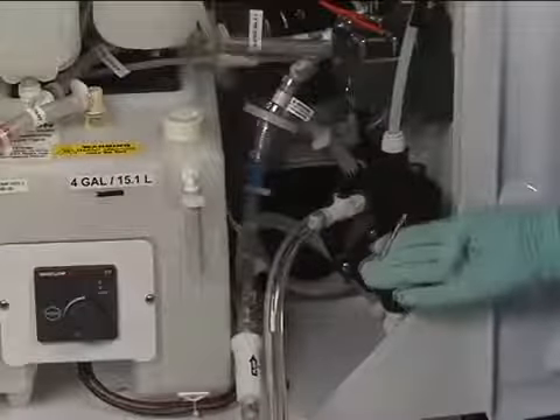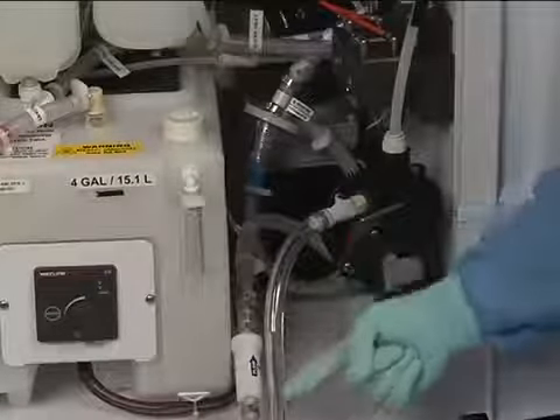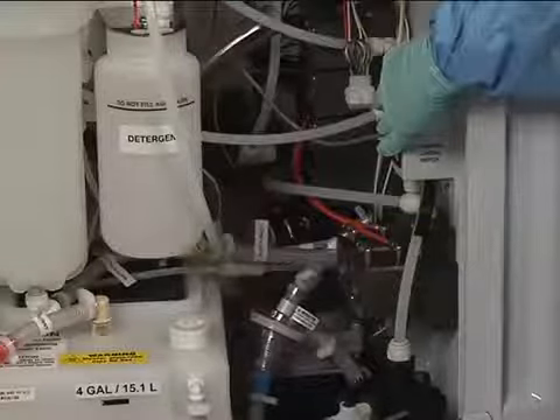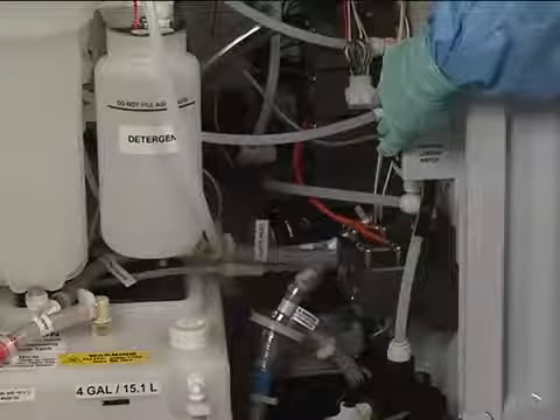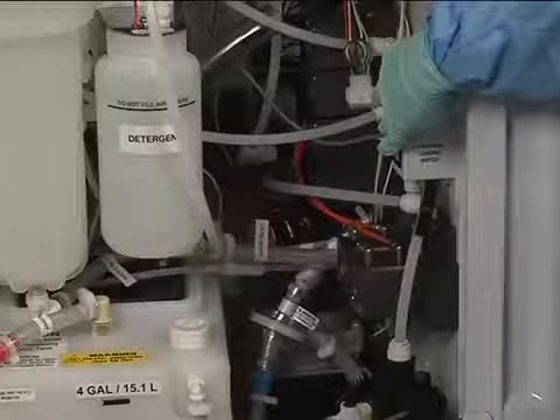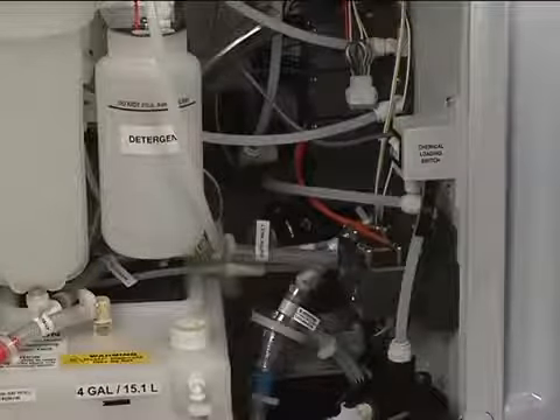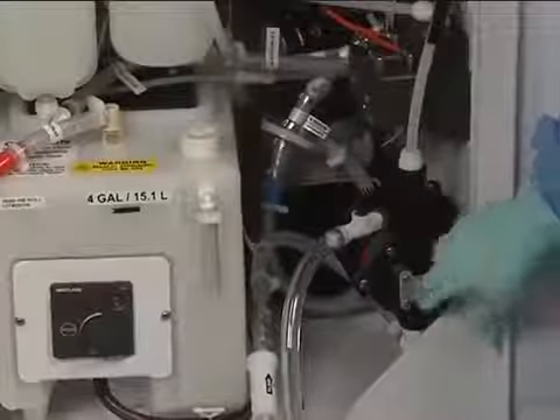Rotate the three-way valve handle of the transfer pump until it points out from the sidewall of the DSD cabinet, which also indicates the direction that fluid will flow, which in this case is into the reservoir. Locate the manual pump switch on the upper right side of the cabinet wall labeled Chemical Loading Switch. Press and hold the switch until all disinfectant has been pumped into the reservoir, and repeat with a new disinfectant container until 4 gallons has been pumped into the reservoir. Rotate the three-way valve handle back and return all tubing connections back to their original positions.